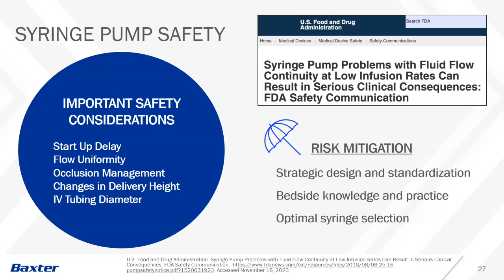An inconsistent rate of delivery can result in serious clinical consequences, as noted in the FDA safety communication shown here. Such consequences include delay of therapy and over or under infusion. Clinicians must recognize the potential safety issues associated with normal syringe pump operation, such as startup delay, potential for post-occlusion boluses, and the impact of tubing diameter. These risks can be mitigated through strategic design and standardization of all processes surrounding syringe pump operation. Also imperative is assuring end user competency so that risks are recognized and managed at the bedside. I will talk in detail about syringe selection next, but I want to highlight the importance of bedside knowledge and practice.